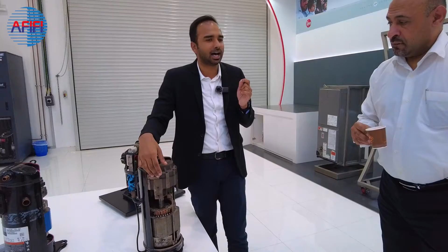Yes, so it has step control, so you can go from 0 to 100. Now these compressors can go up to 120 rotations per second. That's the speed rating, 120, depending on the load, and that load is determined by your indoor units. All of those indoor units give the average capacity need: I need 10, he needs 10. Is it a linear change or linear steps? No, linear change. The step changes are in percentages of 1, 2, 3% like that. In startup it might go to like 15-20% and then go up like that. So all of that is done with these compressors.